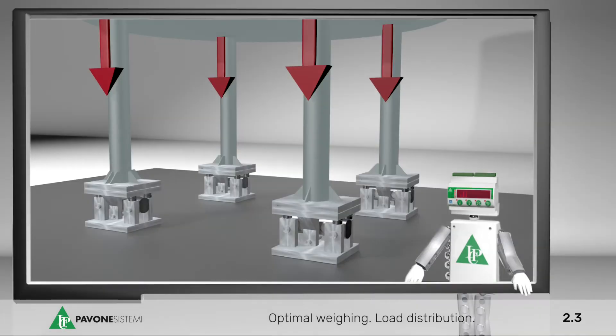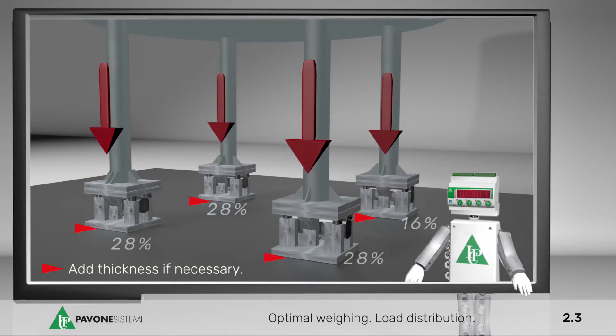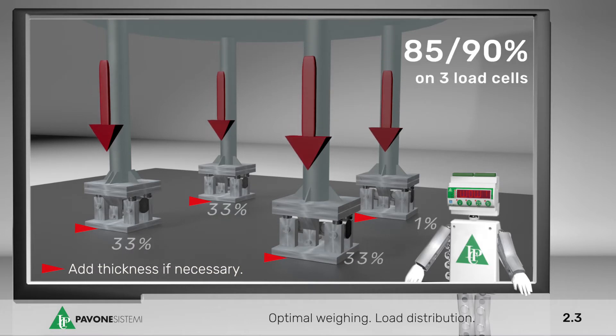Load Distribution. In case of weighing a structure with 4 supports, consider that the load will not be uniformly distributed and that 85-90% of the applied load will be distributed on just 3 supports.